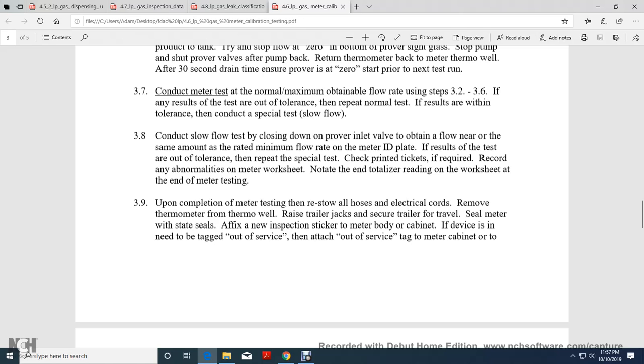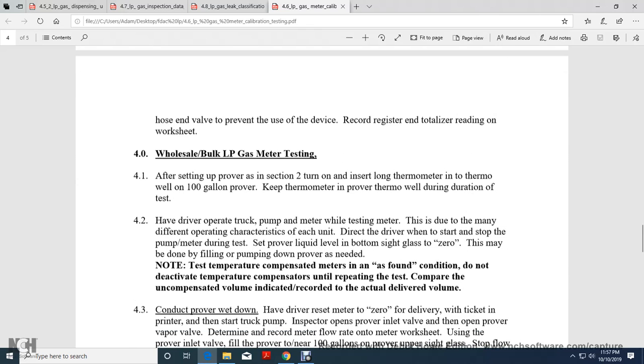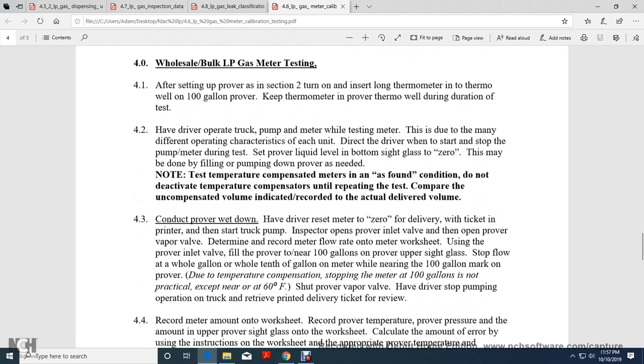After the inspection, place the sticker on the meter body or cabinet. If the device is rejected, attach a tag on the outside of the meter cabinet. Hose over the end valve to prevent the use of the device. Record the totalizer reading on the worksheet.